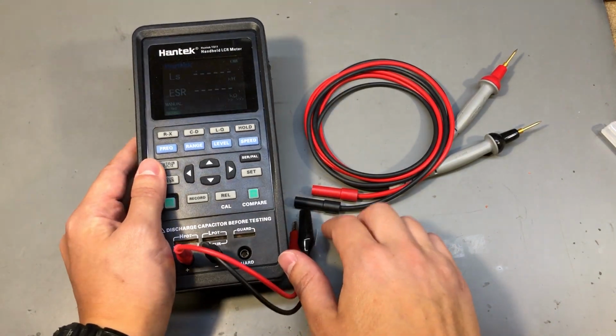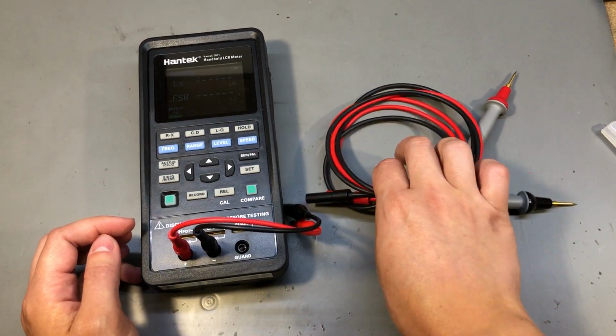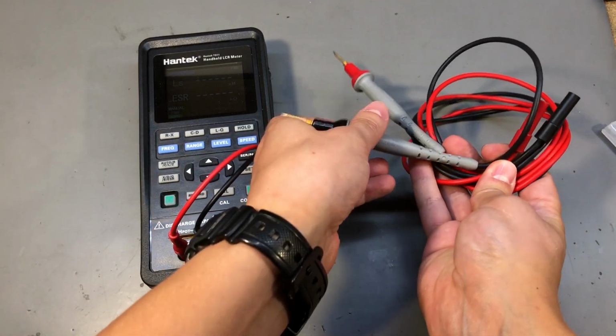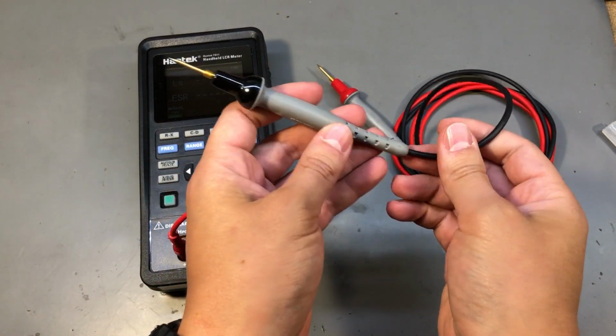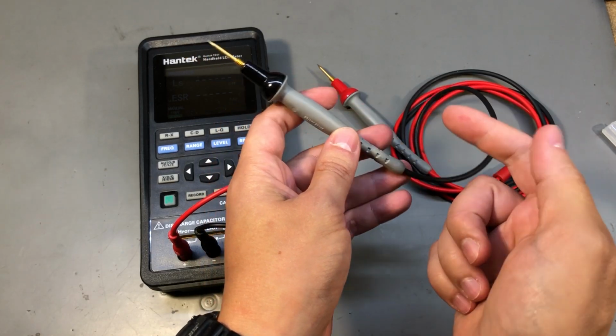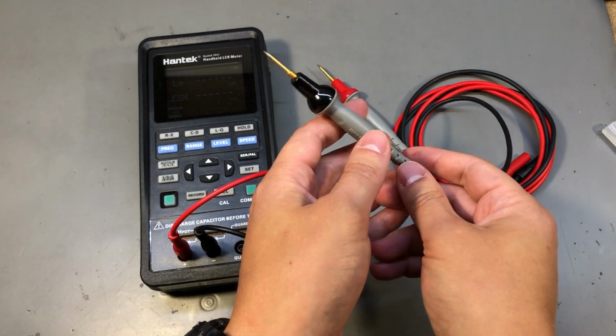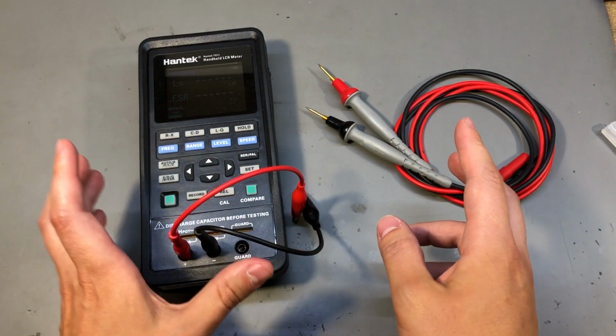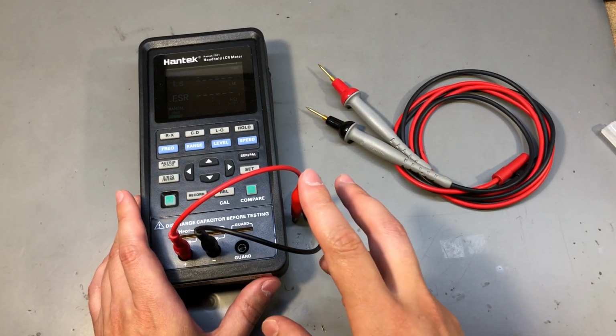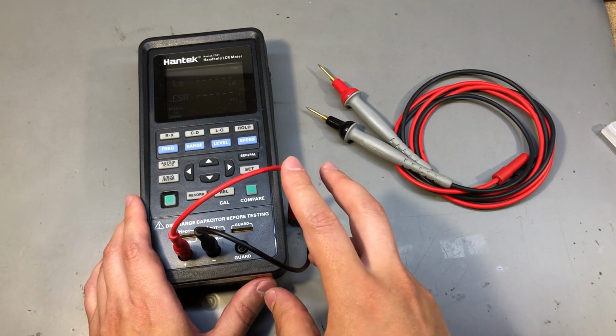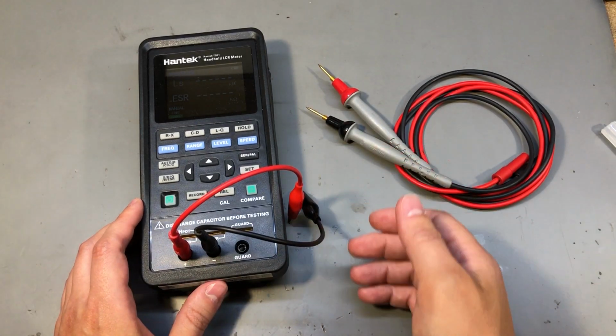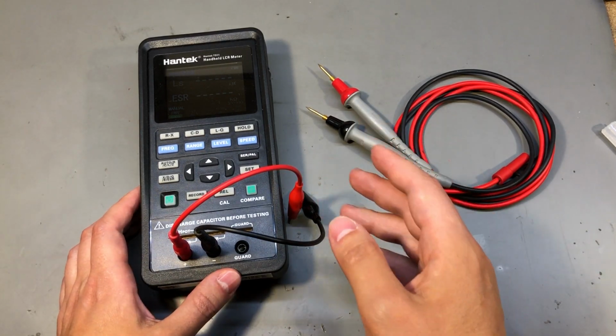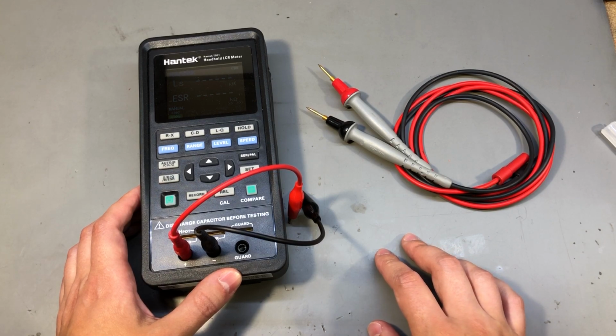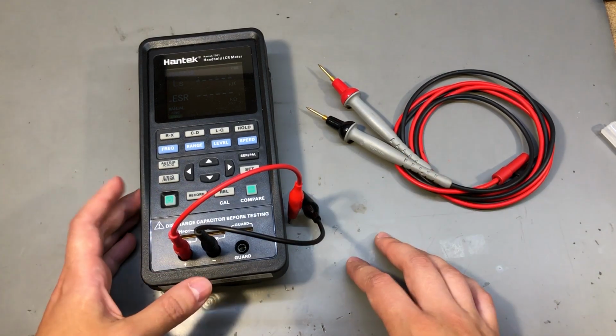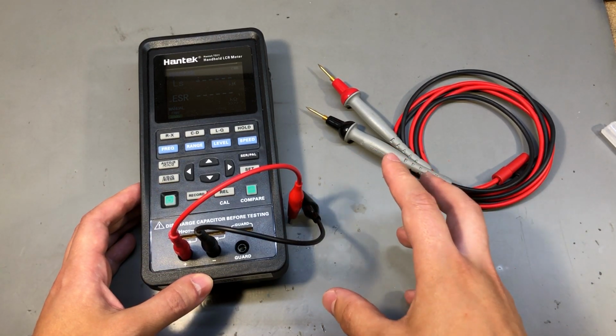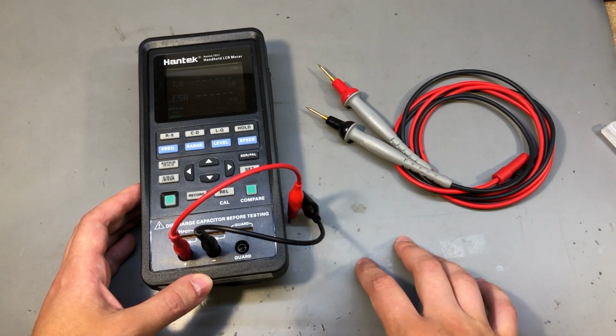If you think about a standard pair of test leads, these will have about 0.1 ohm of resistance per lead. And if you have two of these when doing a measurement, that's 0.2 ohms added to the value you are measuring. Now imagine measuring a 0.1 ohm resistor with that 0.2 ohm included in the measurement. With a 4-wire Kelvin connection, you have two wires carrying the current that's used for the measurement and another two wires doing the sensing, which improves the measurement accuracy.